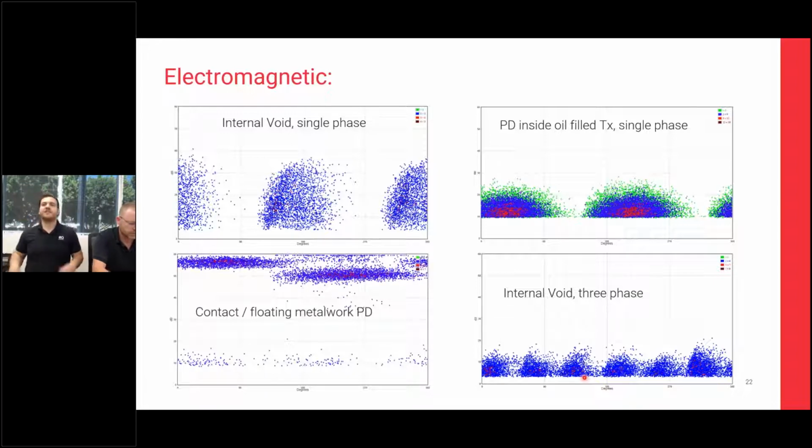So once you start to get activity across multiple phases, you will pick them all up and they will show the separation on the phase plots to correspond with the sine waves. It can blur out a little bit more, but normally you can see them quite well. If you do think you have a three-phase or a two-phase issue, getting that phase lock is absolutely critical, because you can imagine if this starts to blur even a small amount, it can start to just look like noise and you'll lose all of that clustering very quickly.